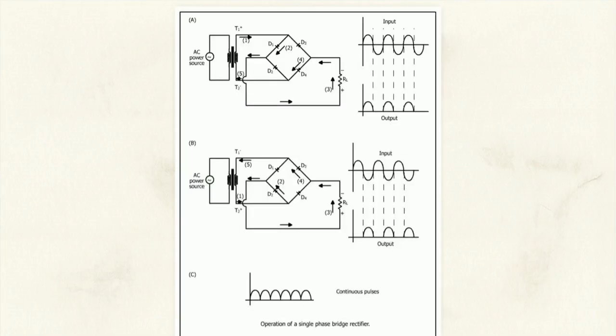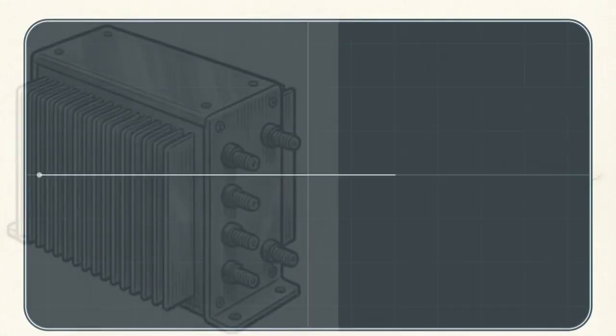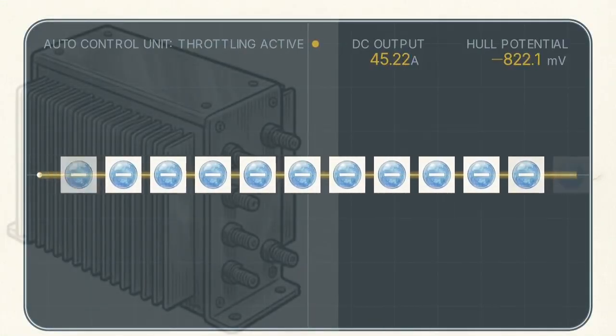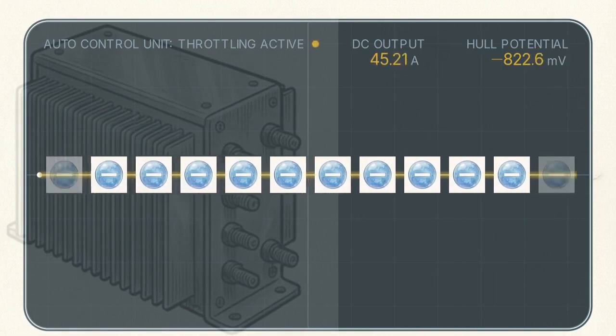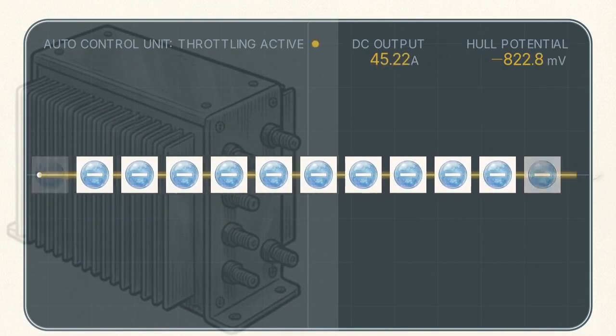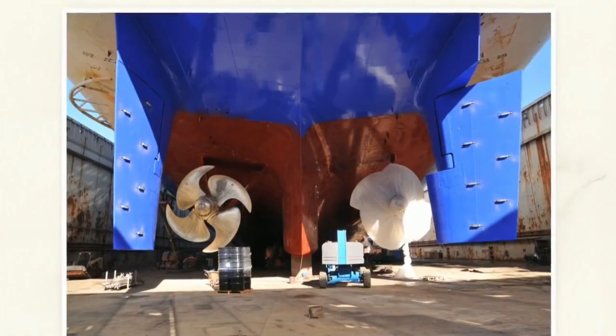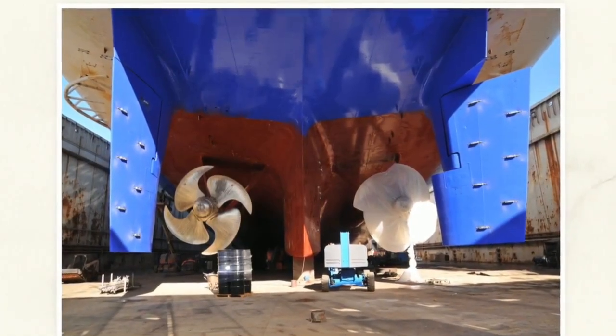This chart shows the next phase. The rectifier bridge takes the stepped-down alternating current and transforms it into the direct current required for the electrochemical barrier. Internal filters then smooth the output, ensuring a steady, continuous pulse of DC power is delivered to the anodes. This precisely throttled direct current is the lifeblood of the protective field, providing the exact number of electrons needed to keep the steel stable.